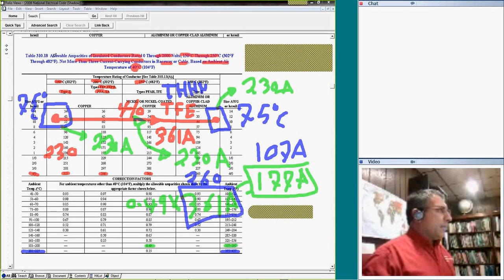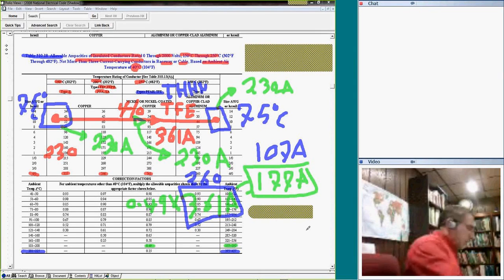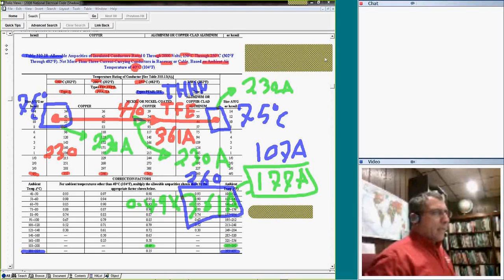But it's good to know that it exists if you have a high temperature application, like in boiler rooms. Places where the temperature can be extremely hot in certain locations. There's a place that can melt steel, and all these industries that create a huge inverter. Always pay attention to it: type Z, TFA, and TFE insulation. So that's basically what I thought about running these.